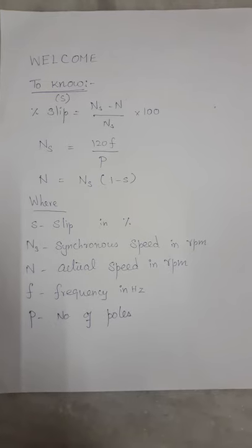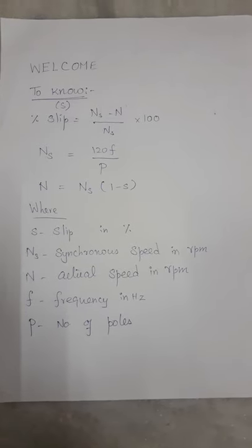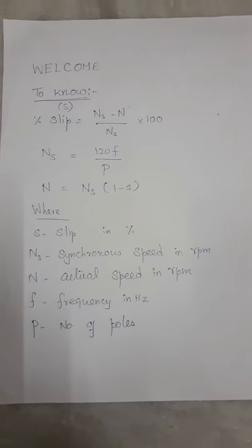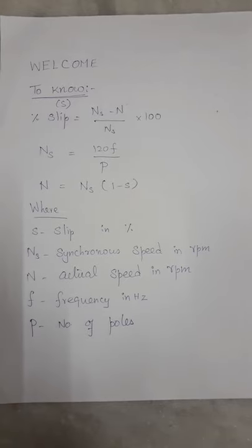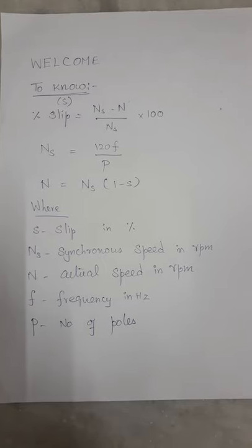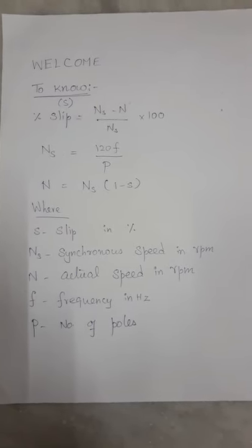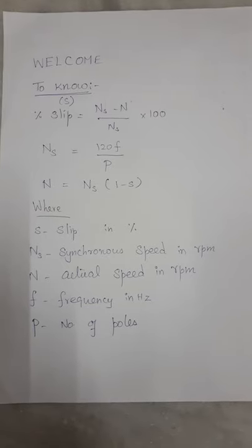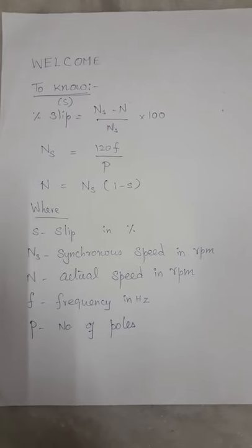Slip in percentage is equal to Ns minus N by Ns, then Ns is synchronous speed 120f by P, then N is actual speed which is equal to Ns into 1 minus S. By knowing these three formulae you can relate all the values and do the calculations very easily.